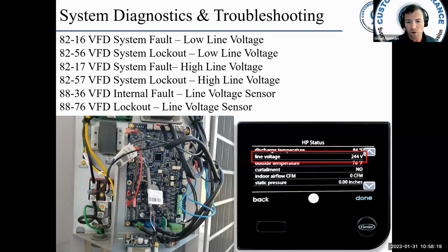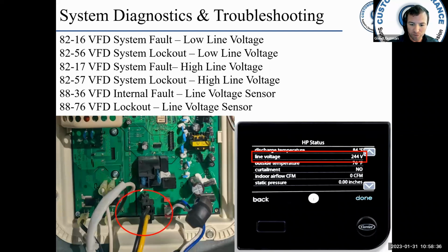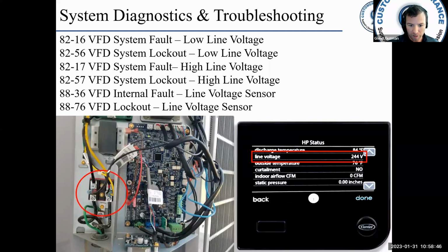8836 VFD internal fault line sensor voltage and 8876 line sensor voltage lockout. These are kind of the same thing. You want to check your voltage at the terminal block, okay, and work your way up to the VFD. Now remember, there is the filter board in between this point here and this point. Okay, you can't really see it from the picture, but kind of right here is that filter board. Okay, the EMI filter board. You could have a failure in that board and giving you a line voltage sensor issue. But you want to make sure you have the right voltage here and then going up to the VFD.